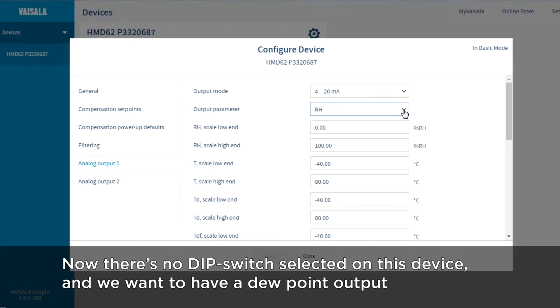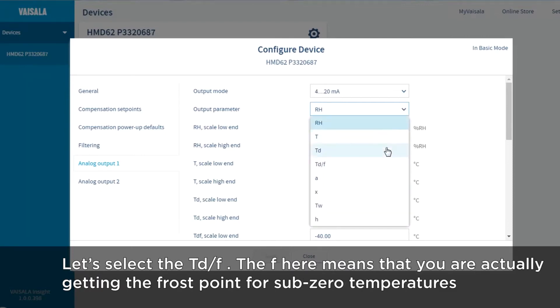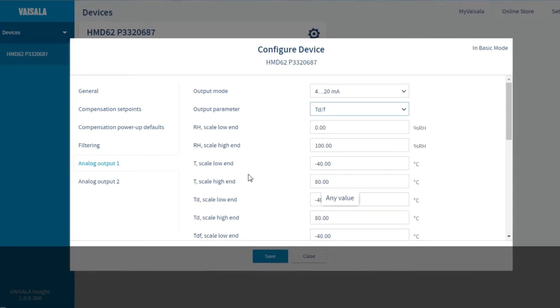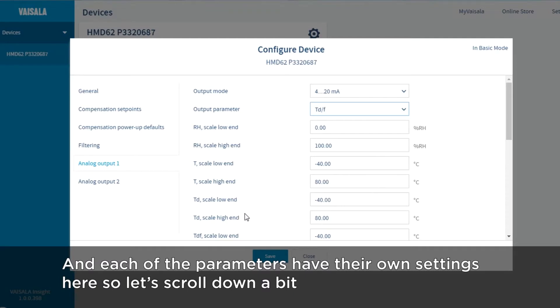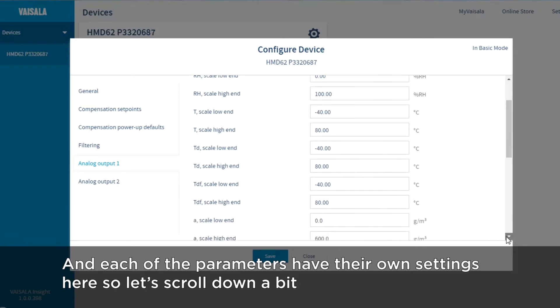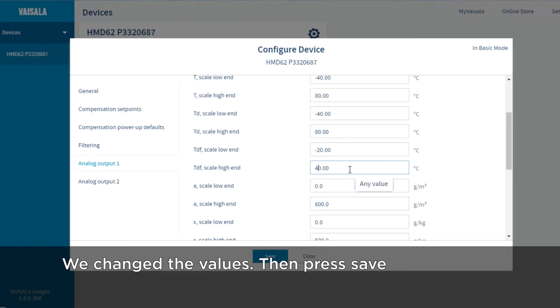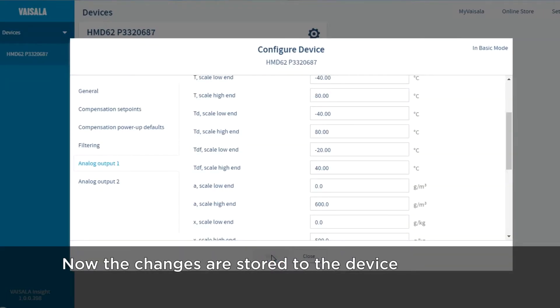Now there is no dip switch selected on this device and we want to have a dew point output. Let's select TD/F here. The slash F means you're actually getting the frost point for sub-zero temperatures, not the dew point — that's the default. Each of the parameters have their own settings, so let's scroll down. We wanted the TDF and we wanted the scale from minus 20 degrees centigrade up to plus 40. We change the values here and press Save. The changes are now stored to the device.